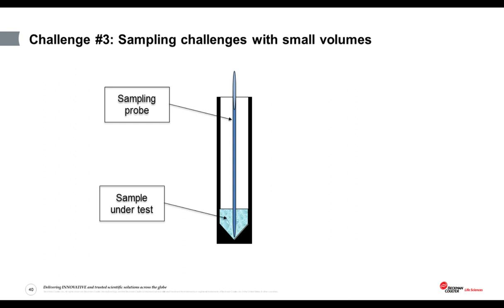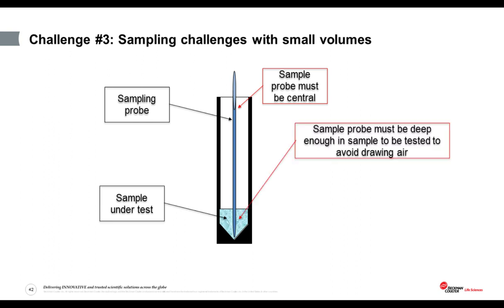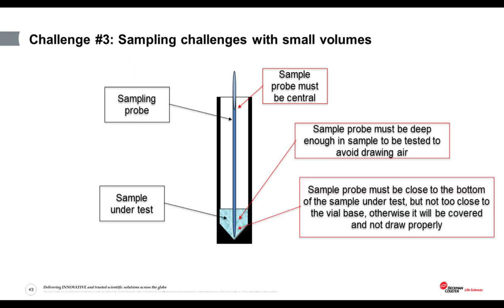The third challenge with light obscuration counters with small volume samples is the positioning of the sample probe inside the vial under test. Ideally, the sample probe should be vertical and central in the vial, especially if the vial is conical. The probe must go down as far into the vial as possible without touching the base of the vial, and the probe must not be allowed to get too close to the surface of the liquid in the vial, otherwise there's a very real risk of drawing air into the sample. And of course, air bubbles will be counted as if they were particles by the light obscuration counter, so you could get a false positive there, a higher count than you're expecting because the counter's drawing air. So really, holding a probe by hand while sampling in a very small sample makes it very difficult to avoid these problems, especially if trying to complete the whole test with just 1 milliliter of product.